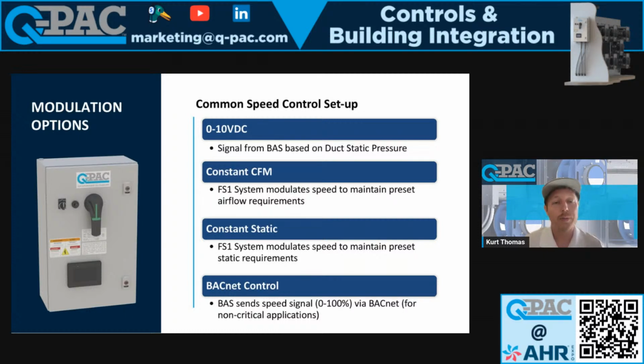All right, so another option is constant static. So if you have a critical application where you don't think that your BAS is very reliable, or maybe you don't have a BAS yet, and you want to maintain duct static pressure, then you can tie in a static pressure sensor 2/3 of the way down the duct, at the end of the duct, wherever you want. As long as it has an output of 0 to 10 volts, you can tie it back to our control panel. And then again, set the constants on the PID loop so that it ramps up and down at the correct rate. But we can maintain your duct static pressure for you.